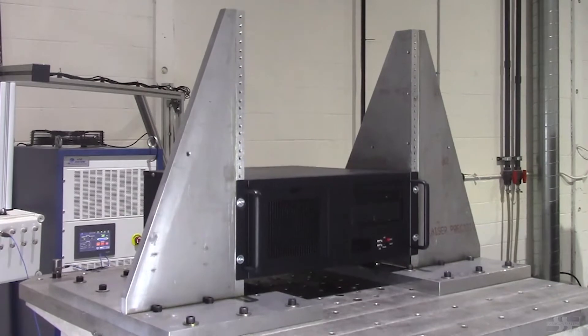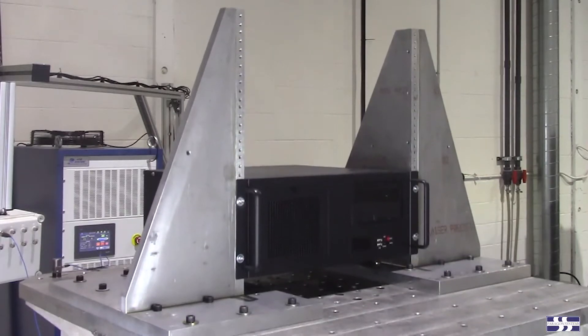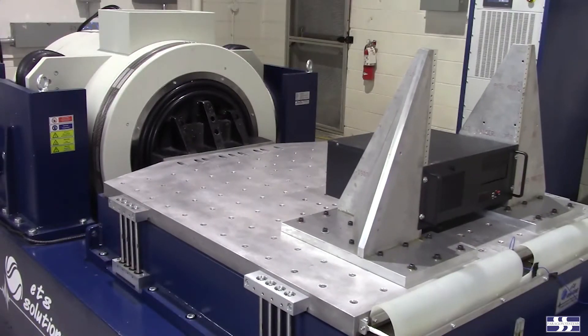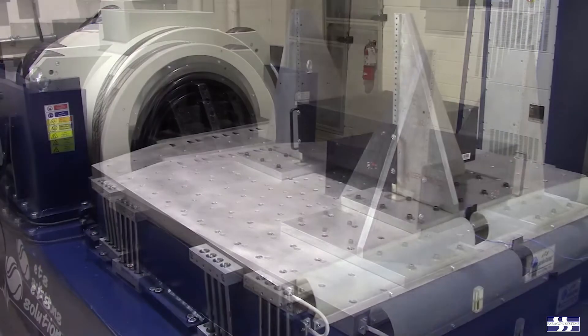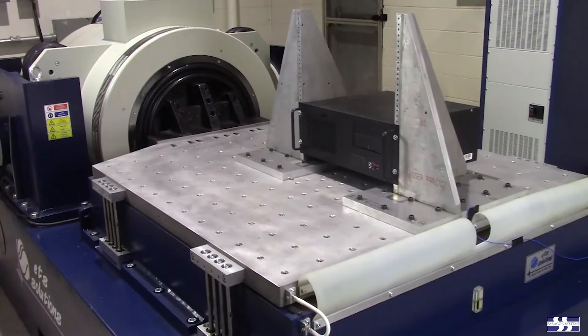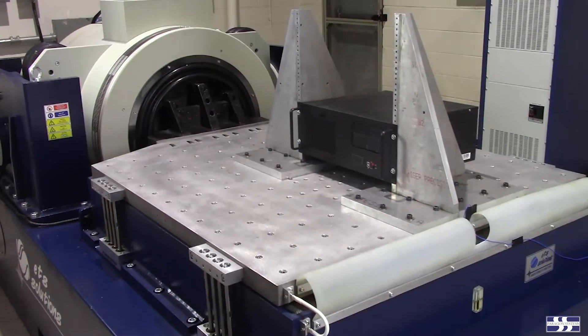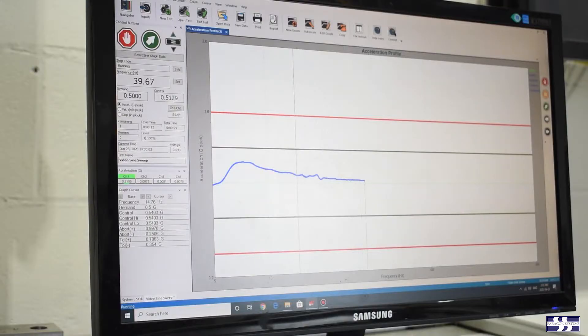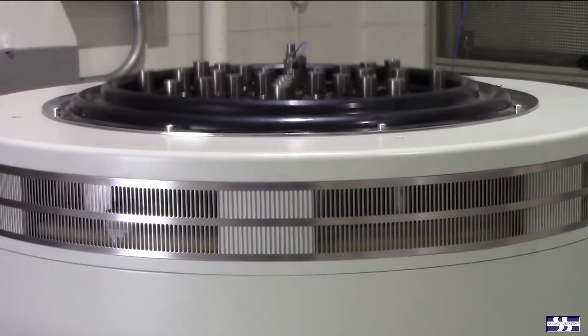Most vibration tests rely on a vibration fixture to connect the test device to the laboratory's shaker table surface. The outcome of the vibration test can be influenced by fixture resonances or attenuation.